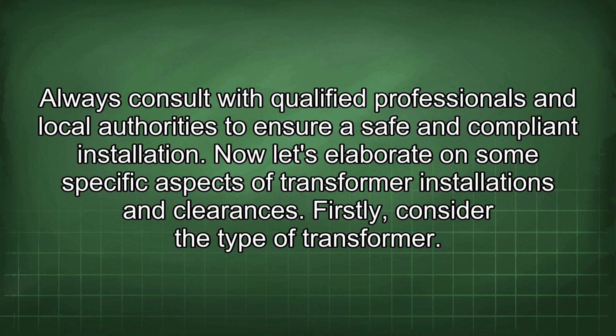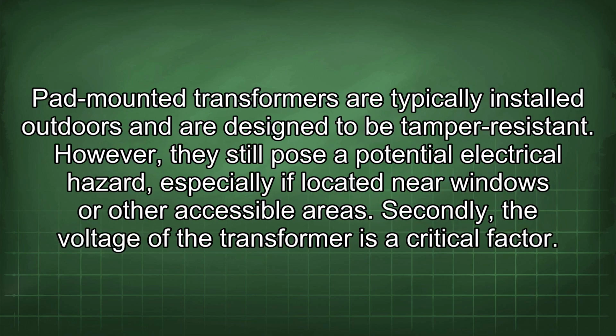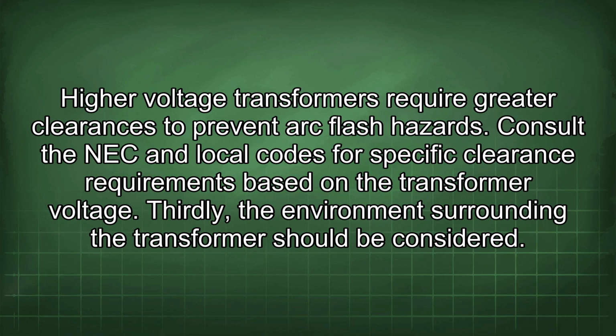Now let's elaborate on some specific aspects of transformer installations and clearances. Firstly, consider the type of transformer. Pad-mounted transformers are typically installed outdoors and are designed to be tamper-resistant. However, they still pose a potential electrical hazard, especially if located near windows or other accessible areas. Secondly, the voltage of the transformer is a critical factor. Higher voltage transformers require greater clearances to prevent arc flash hazard. Consult the NEC and local codes for specific clearance requirements based on the transformer voltage.